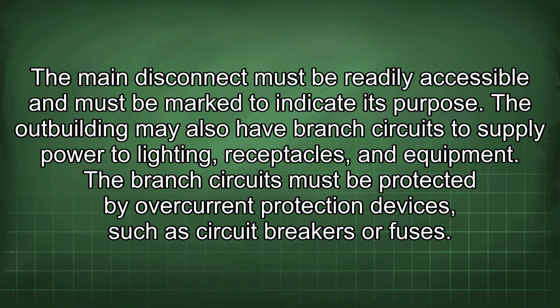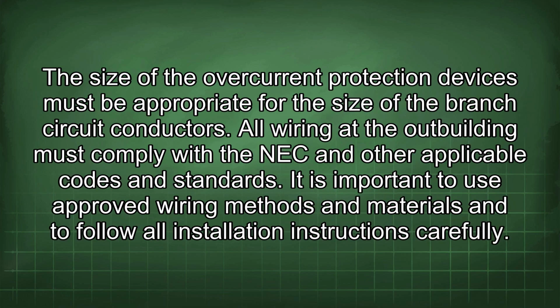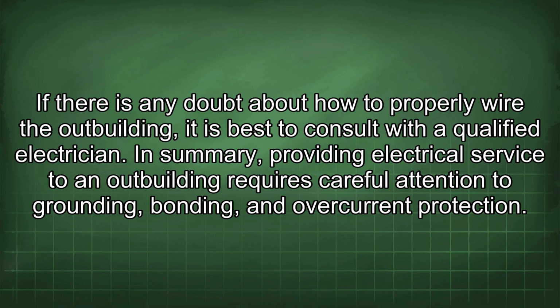The outbuilding may also have branch circuits to supply power to lighting, receptacles, and equipment. The branch circuits must be protected by overcurrent protection devices, such as circuit breakers or fuses. The size of the overcurrent protection devices must be appropriate for the size of the branch circuit conductors. All wiring at the outbuilding must comply with the NEC and other applicable codes and standards. It is important to use approved wiring methods and materials and to follow all installation instructions carefully. If there is any doubt about how to properly wire the outbuilding, it is best to consult with a qualified electrician.